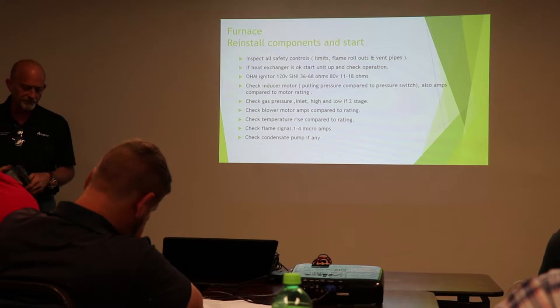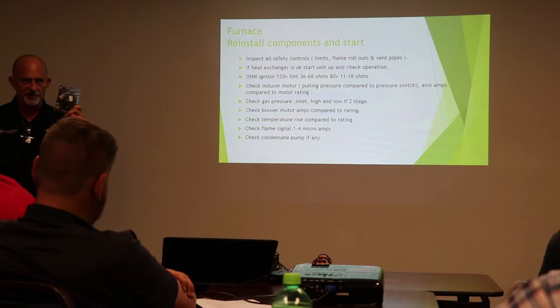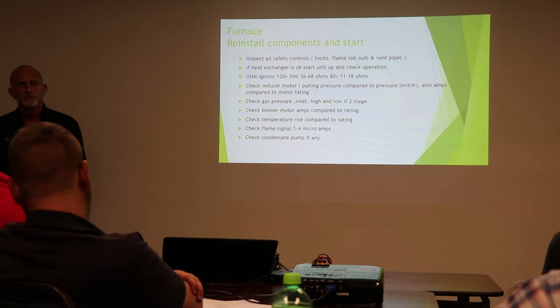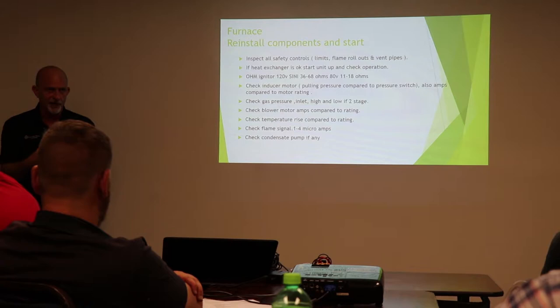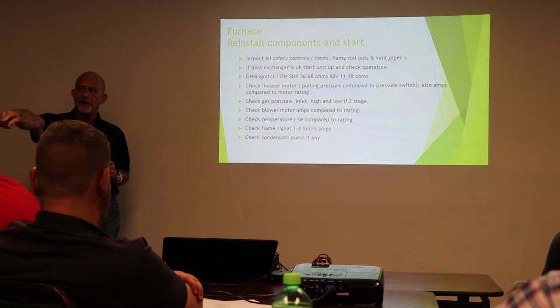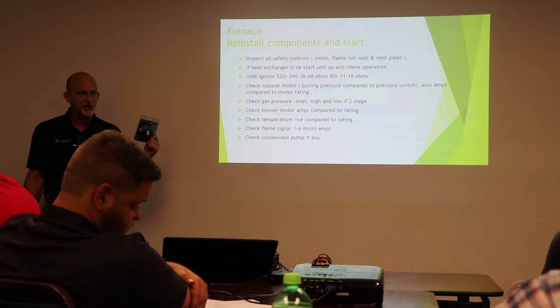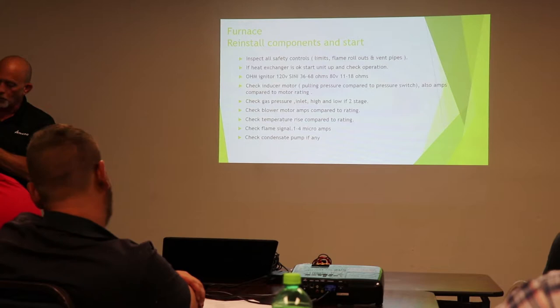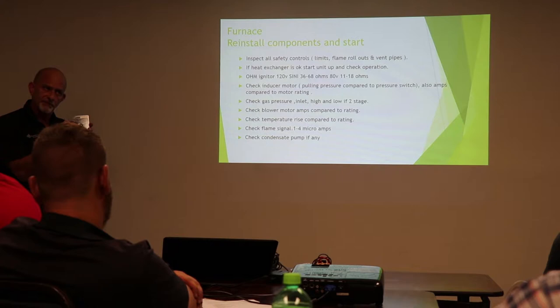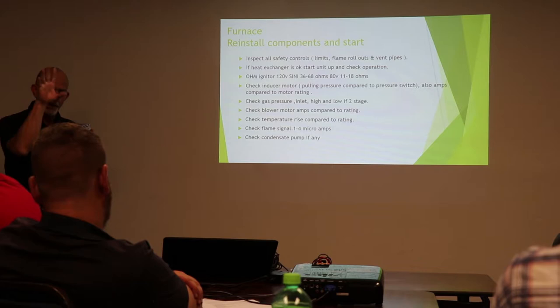Now, we're supposed to set this pressure switch to what the original pressure switch closes at. How do we know? Some guys suck on their manometer, try to get a reading, try to close this. With that manometer, with a vacuum pump in it, put it to your test mode, turn it up to what the old pressure switch is. You're going to plug your two wires onto your pressure switch, your hose onto your port, and then you take your little Allen wrench to set it, and it gets to where your vacuum pump pressure is set at, the light comes on. Now it's set to the proper pressure.